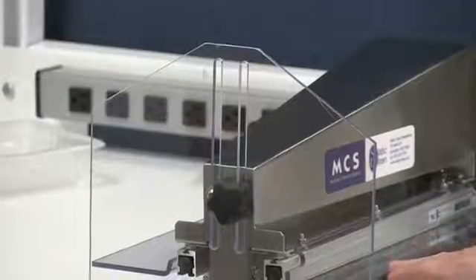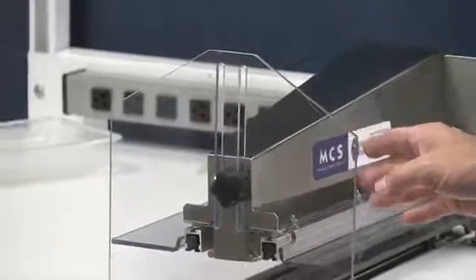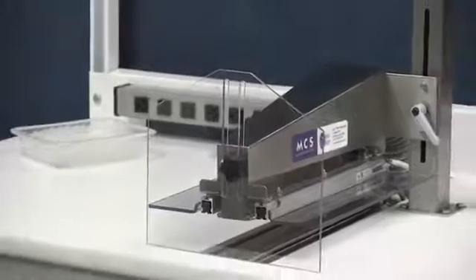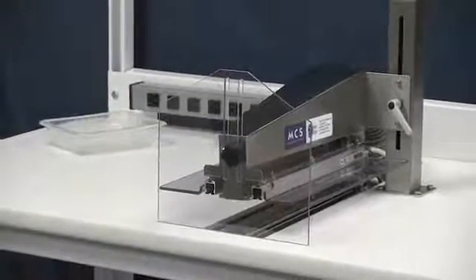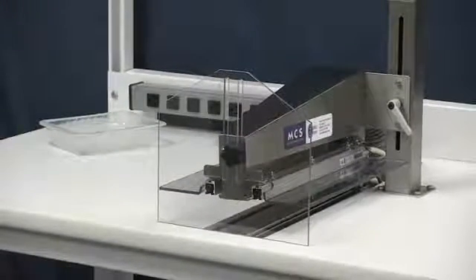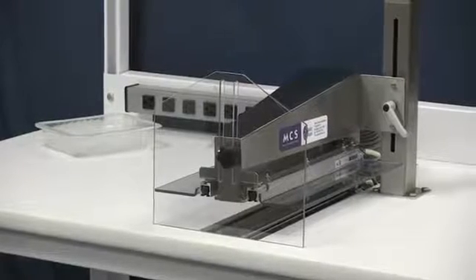Clear polycarbonate air baffles envelop the cleaning zone creating a tunnel effect around your product to maintain high velocity airflow across a wide footprint to effectively capture those particles while providing good visibility.